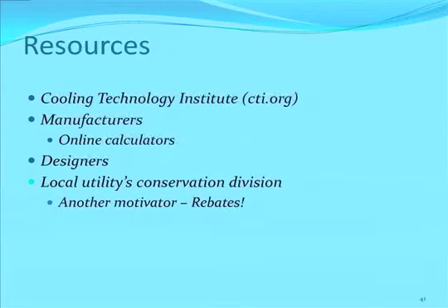And keep in mind that because it's a heat transfer device, if you have a good system and you keep it clean, you're going to keep transferring the heat the way that you need to. It's going to save energy, but it's also going to save water because you're going to have less run time trying to reject that heat. Some resources are the Cooling Tower Institute. The manufacturers, some of them have online calculators, designers, and then talking to your local electric utility, as far as another motivator, which is what I do.